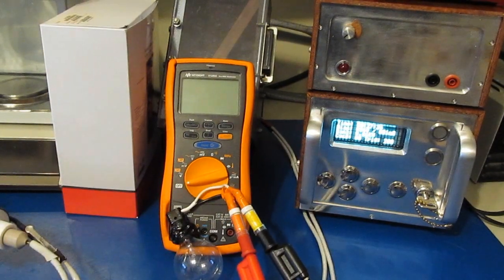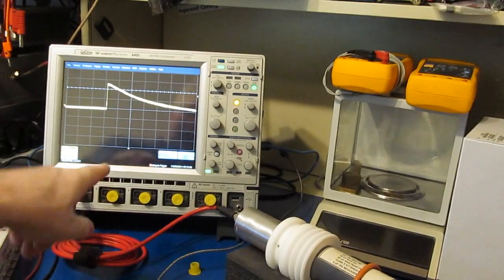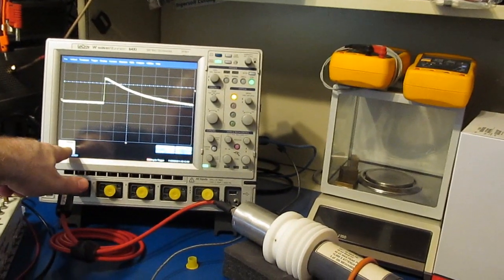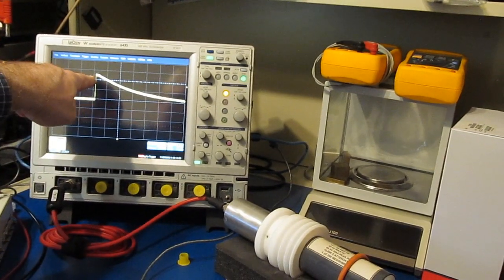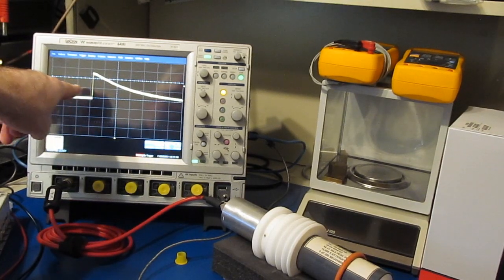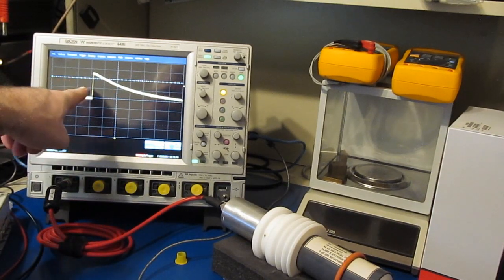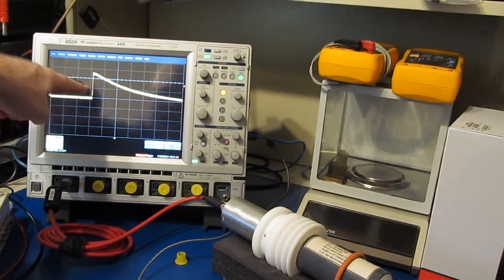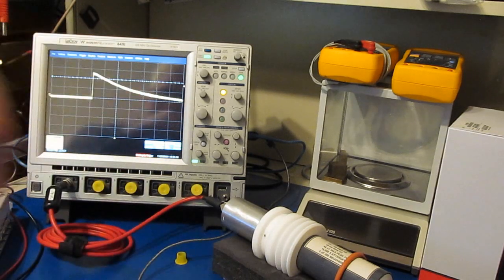So I've changed our generator and our scope. Now we are currently set for 1,000 volts per division. You can see we're 2.5 divisions up, or 2,500 volts. Again, it's 50 microseconds per division. If we look over here, again, it's 100 microsecond full width half height.